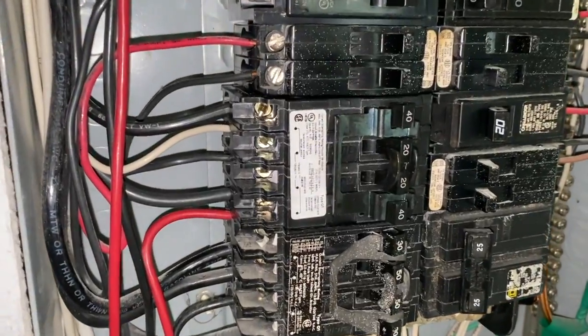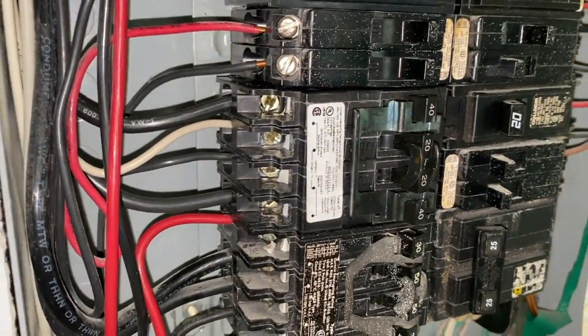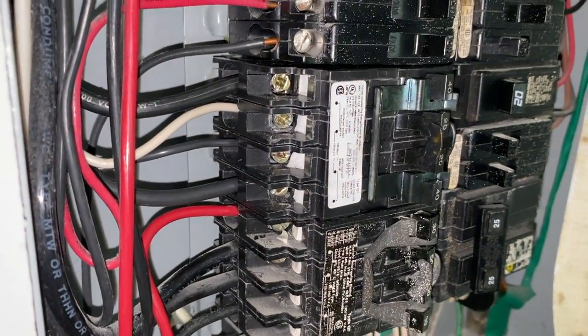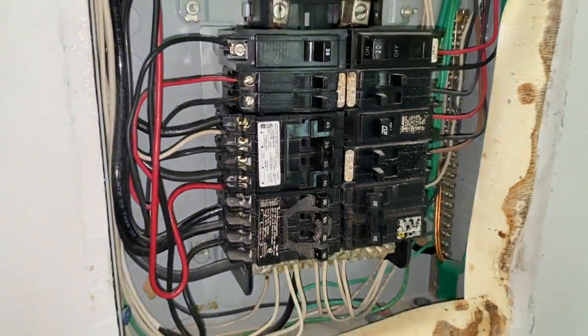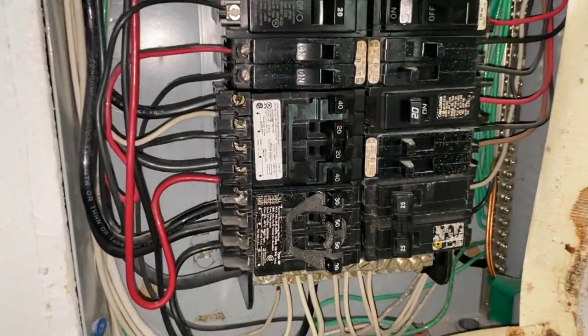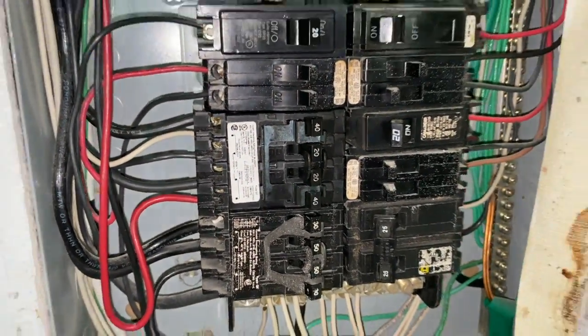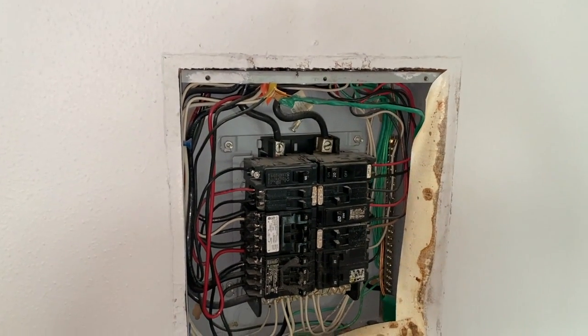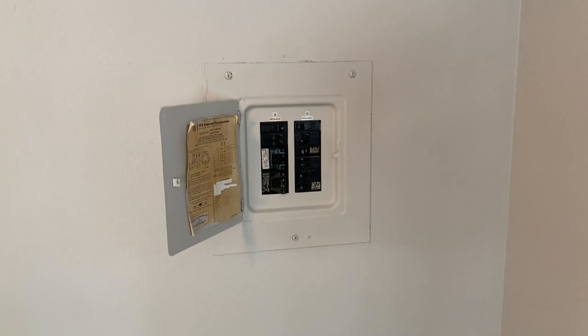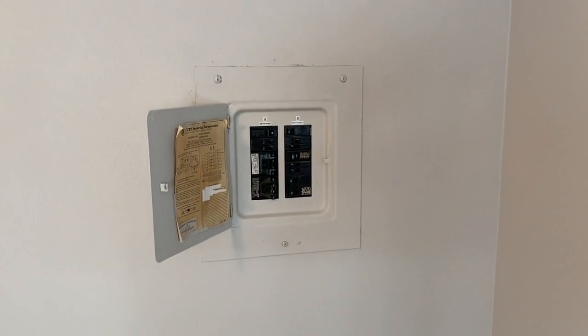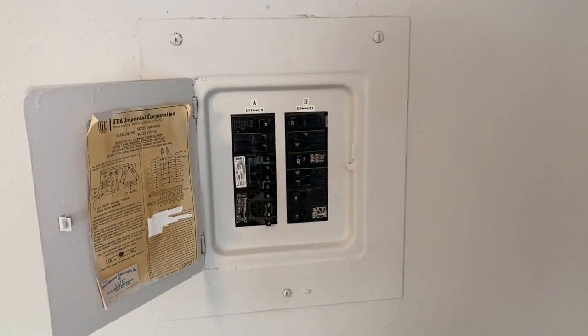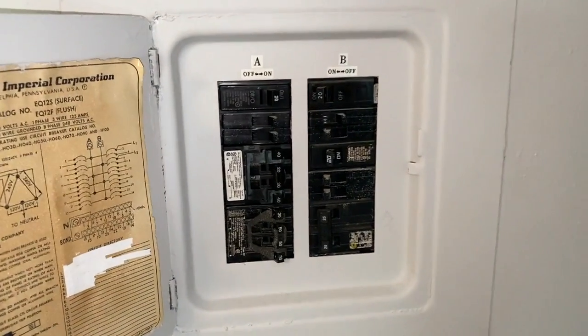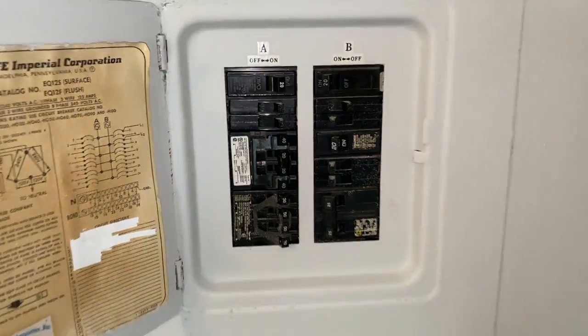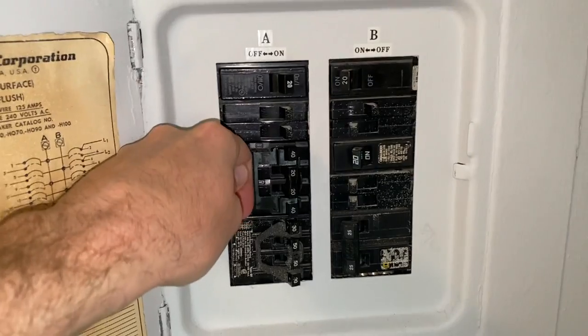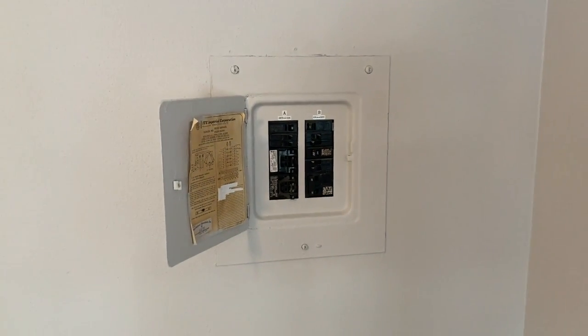To a closer view, and again, electricity has been restored and the breaker is up and running and in use and operation. And again, just double check everything and monitor that new breaker as well as the wiring over the next few days to ensure nothing is out of the ordinary. And from here, we will re-secure the panel plate and door. Take a step back, and the cover plate as well as the door is re-secured to the panel, and DIYers, that is it. However, again, over the next few days, just monitor the operation of the breaker and make sure there is no vibrating or humming sounds. Make sure that the breaker itself is not warm or hot. And again, that's it. We hope this helps.